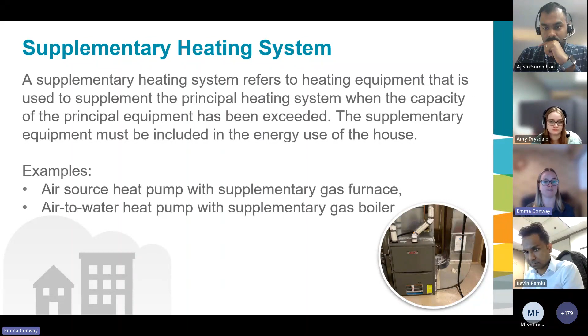I think it's really important to understand, when selecting your equipment, when talking to your energy advisor to do the modeling, and when talking to your HVAC contractor who's purchasing and setting up the equipment, to understand the cutoff temperature. What is the cutoff temperature? Also referred to as a switchover temperature, this is the minimum operating temperature for the primary heat pump system. For example, your off-the-shelf heat pump will probably operate to about 0 degrees Celsius. That's the cutoff temperature, and then the supplementary system would kick in.